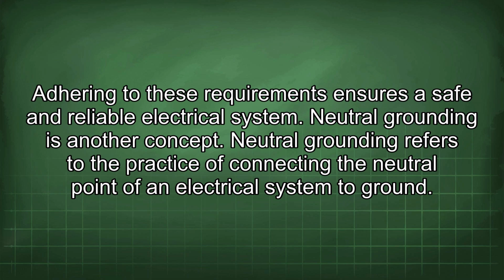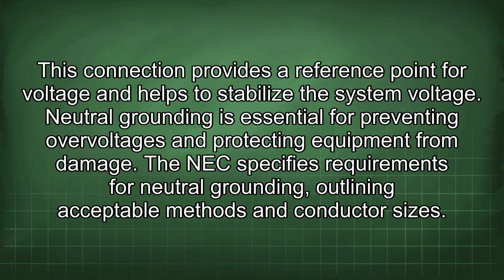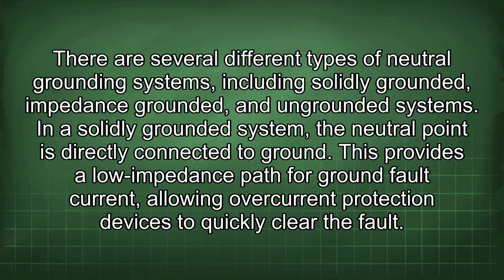Neutral grounding is another concept. Neutral grounding refers to the practice of connecting the neutral point of an electrical system to ground. This connection provides a reference point for voltage and helps to stabilize the system voltage. Neutral grounding is essential for preventing overvoltages and protecting equipment from damage. The NEC specifies requirements for neutral grounding, outlining acceptable methods and conductor sizes. There are several different types of neutral grounding systems, including solidly grounded, impedance grounded, and ungrounded systems.